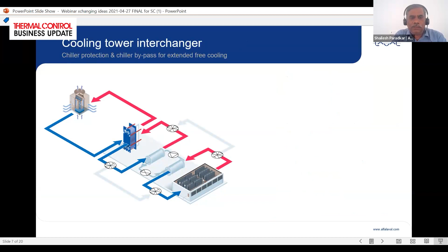As all of us know, as temperature increases, your scaling tendency also increases, because the calcium carbonate, whatever small content is present in open type cooling towers, will precipitate in the condenser, which is a hot surface because the other side is discharge gas. So what we promote is that you put a heat exchanger in between, which will act as a cooling tower interchanger. So you can have this fouling in the condenser minimized or even nullified, where the closed loop water will move through the condensers and have no tendency for fouling, and your condenser will work as per the specification with lower discharge pressures, and you will have lower power consumption.